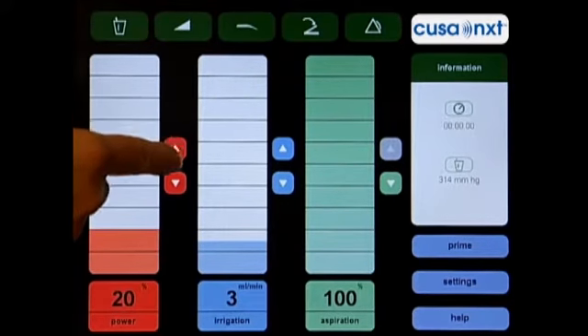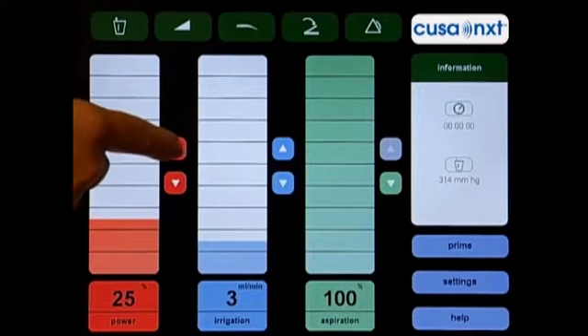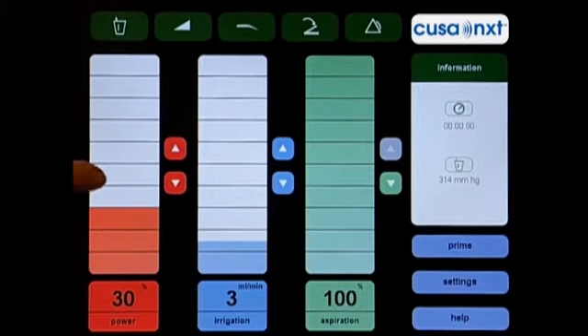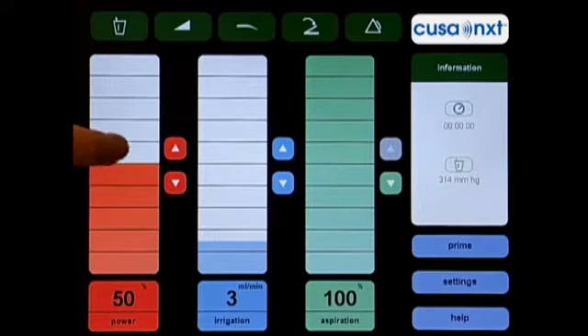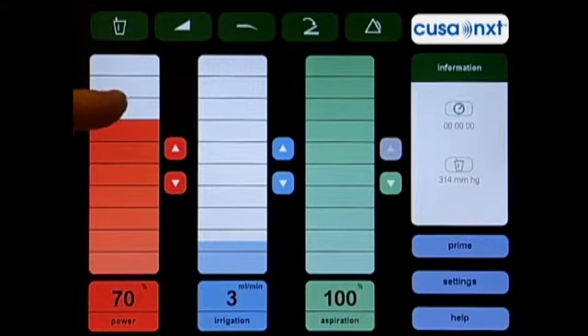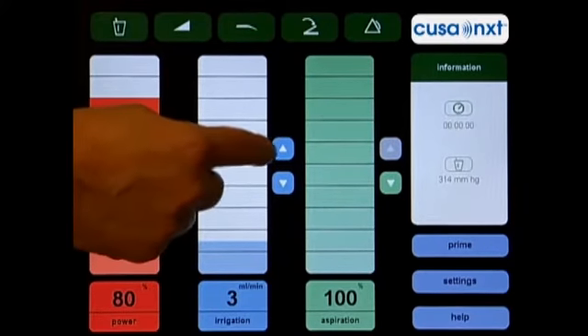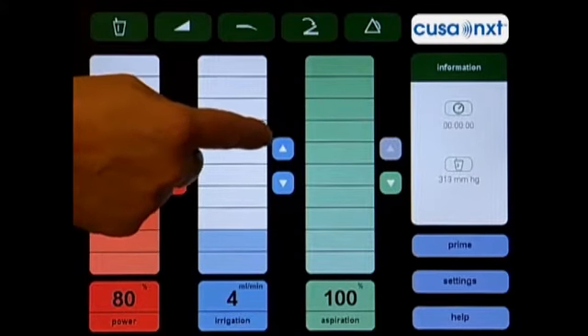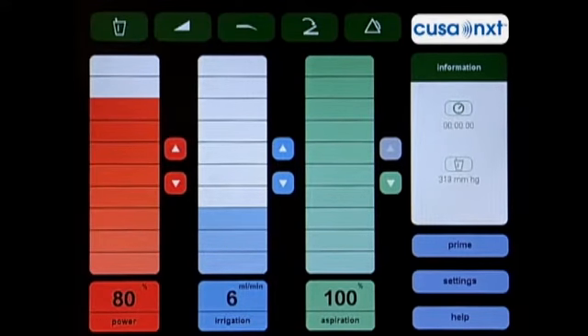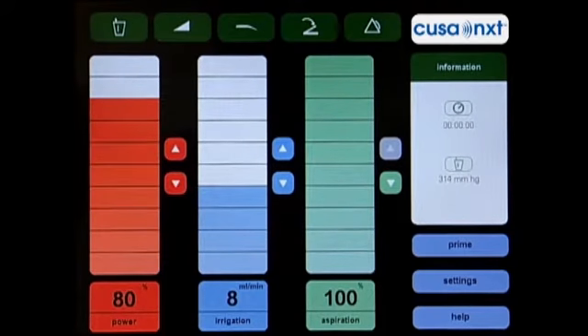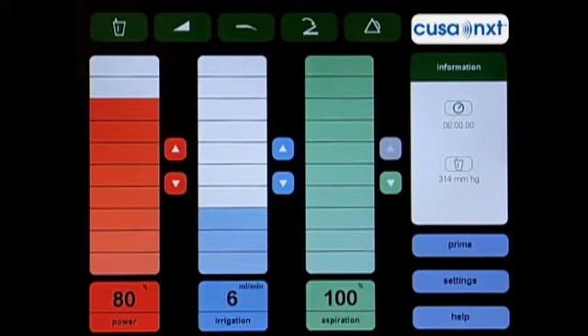Touch of the orange up or down arrows will increase or decrease the power setting by 5%. Touching the power level scale will increase or decrease the setting by 10%, with each touch above or below the current level. Typical power settings are between 70% and 100%. When adjusting the irrigation level, each touch of the blue arrows will increase or decrease irrigation by 1 milliliter per minute. Touching the irrigation level scale will increase or decrease the setting by 2 milliliters per minute. Typical irrigation settings are between 2 milliliters per minute and 8 milliliters per minute.